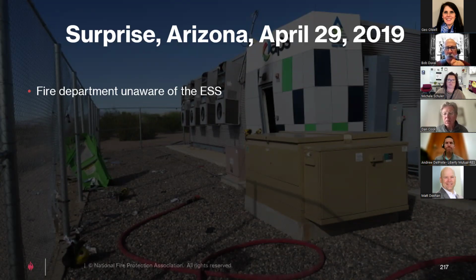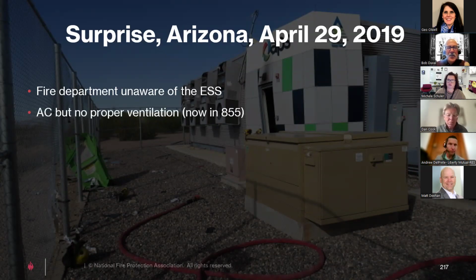The fire department wasn't aware it was out there. They got a call for smoke in the area and thought it might be a brush fire given how remote it was. They showed up and saw the smoke was coming from this unit, so they upgraded the response to a hazmat. The utility representative showed up but wasn't able to tell them much about what was going on inside. So they did research for three hours, metering all around the installation. There was air conditioning, but not proper ventilation inside, and I'm pretty sure the air conditioner shut off when the gaseous suppression system activated inside the energy storage.